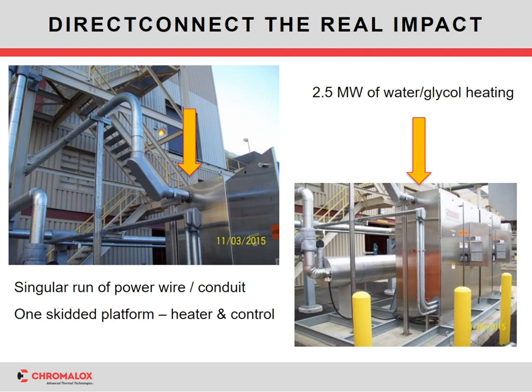So DirectConnect, how does it save you? By the use of medium voltage, we're able to cut down on the wiring and the installation cost, and we'll show some of the numbers coming up shortly. In these pictures, if you look at the highlighted areas, this is a 2.5 megawatt system that was used for water glycol heating in a power plant. And rather than having those multiple runs of wires and raceways and transformers, you can see there's simply one conduit connection to bring that power wiring run into the heater. That greatly simplifies the installation cost and time for such a system, and you can provide all that on one common platform versus the prior system that you saw with multiple platforms and runs in between, and real estate.